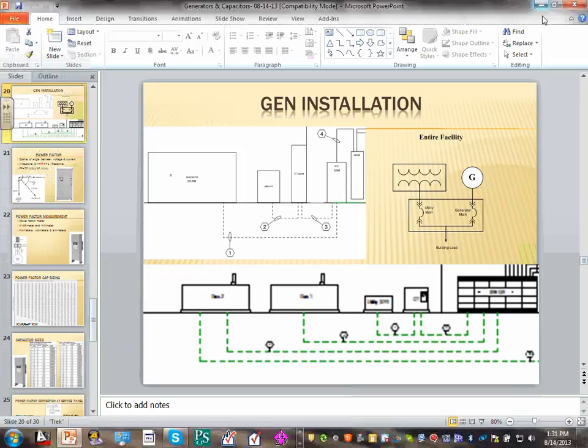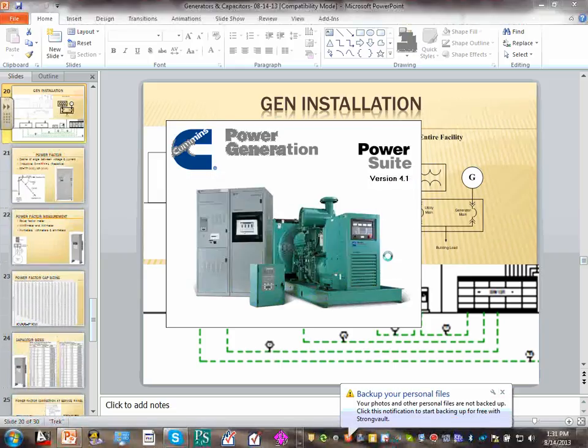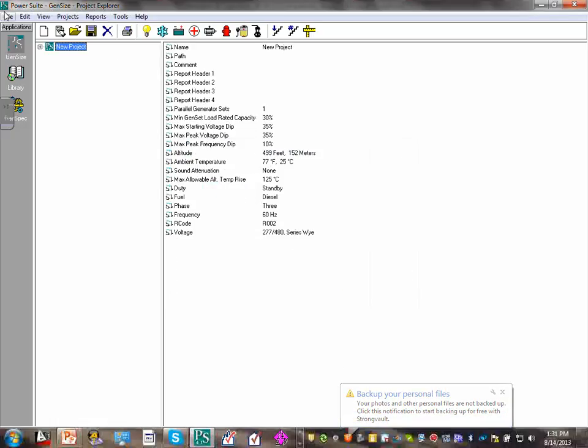Yeah, you can't have the generator exhaust near an air intake or operable windows and all that, but it also has to function. You don't have the operable windows at all. But they could have had an air intake for the HVAC system, but you have to be at a specific distance away from it.